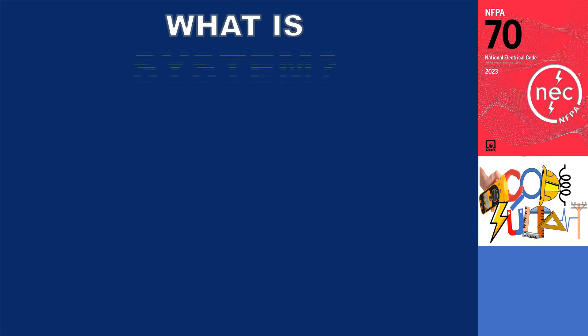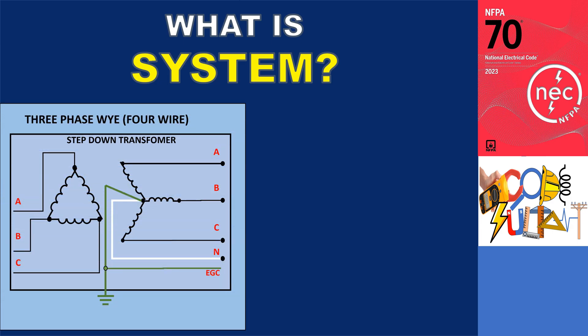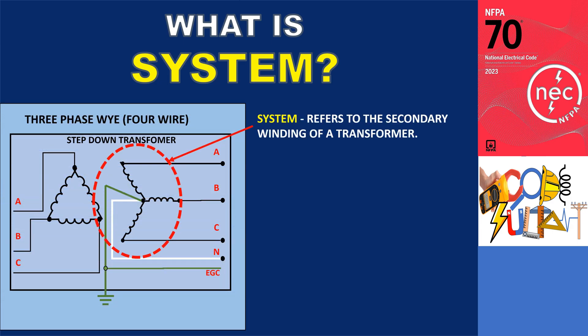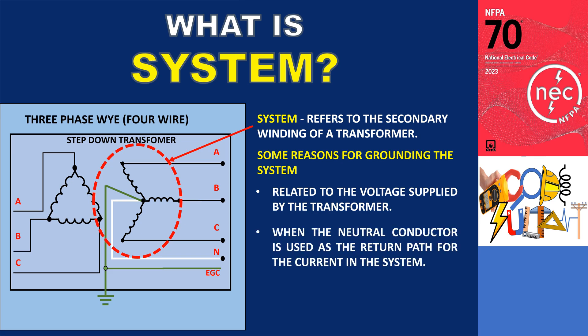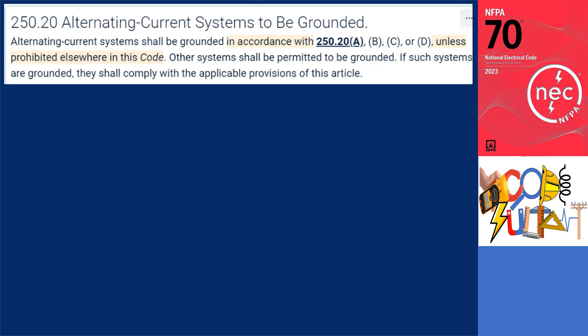In our discussion, the term 'system' specifically refers to the secondary winding of a transformer. One of the primary reasons for grounding the system is directly related to the voltage supplied by the transformer. In certain situations, grounding becomes necessary when the neutral conductor is used as the return path for the current in the system. Section 250.20 states that alternating current systems shall be grounded in accordance with 250.20 A, B, C, or D, unless prohibited elsewhere in the Code.